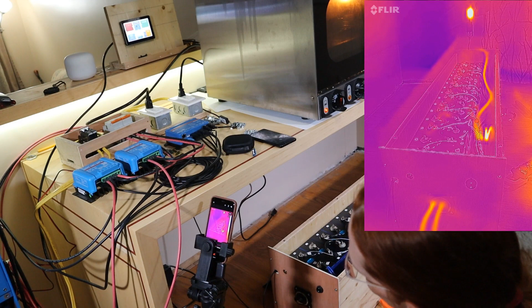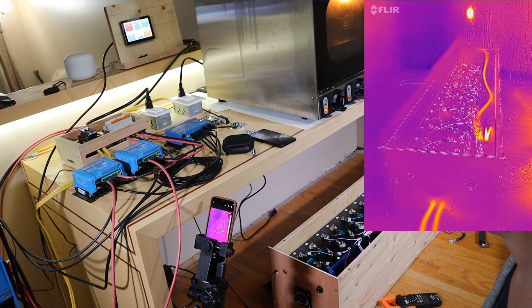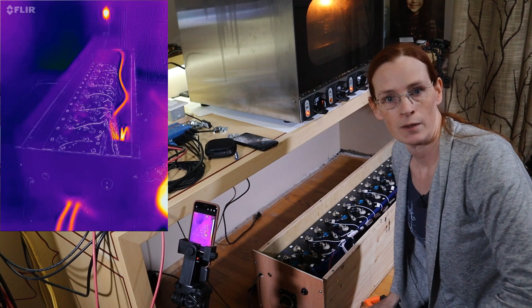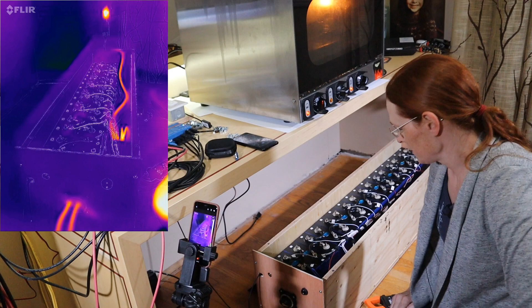6 minutes to go, still pulling 2,800 watts, 53.6 amps. No visible heating at all from the flexible bus bars. The long wire is warming up, but all of the actual jumpers are perfectly cool. Better than the rigid bus bars. The fact that I'm seeing the long run start to warm up and nothing on these flexible bus bars - yeah, I think this is a winner. I really think this is a winner.